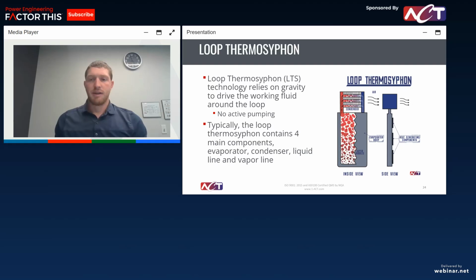Depending on your ultimate heat sink, there's really two main heat exchangers we'll use. One will be a liquid to air heat exchanger, which is shown here. We'll typically use the tube and fin style, where we're blowing ambient air across it. That's going to cool that fluid back down, condense it, and it will return back.